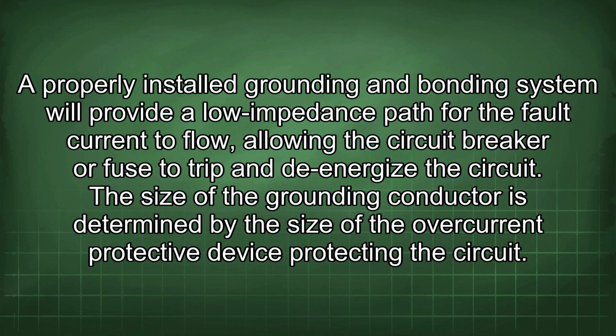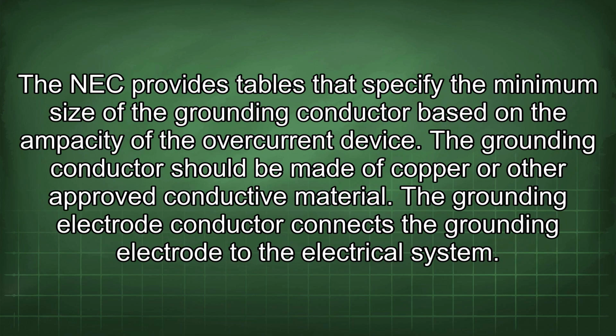The size of the grounding conductor is determined by the size of the overcurrent protective device protecting the circuit. The NEC provides tables that specify the minimum size of the grounding conductor based on the ampacity of the overcurrent device. The grounding conductor should be made of copper or other approved conductive material.